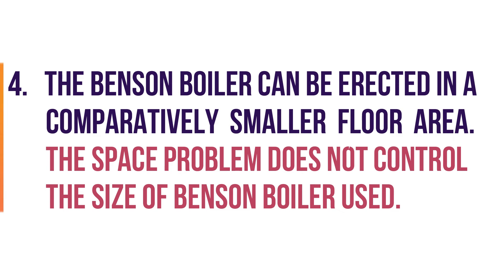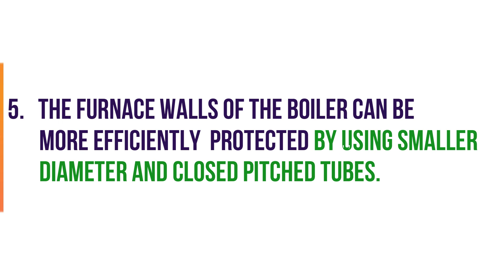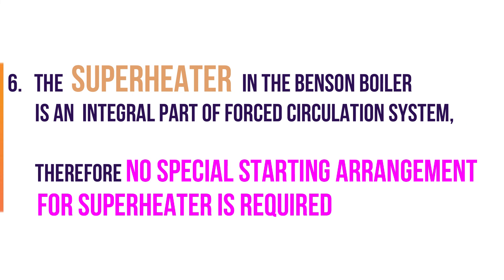Fourth advantage: the Benson boiler can be erected in a comparatively smaller floor area, and space problems do not control the size of the boiler. Fifth advantage: the furnace walls of the boiler can be more efficiently protected by using smaller diameter and close pitch tubes. Sixth advantage: the superheater in the Benson boiler is an integral part of the forced circulation system, so no special starting arrangement is required for the superheater.